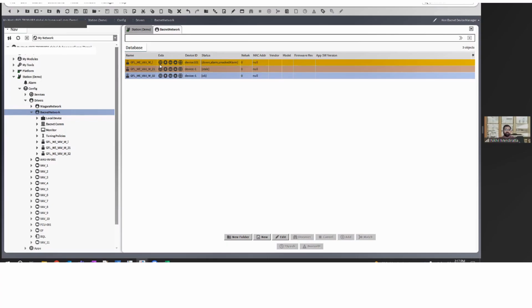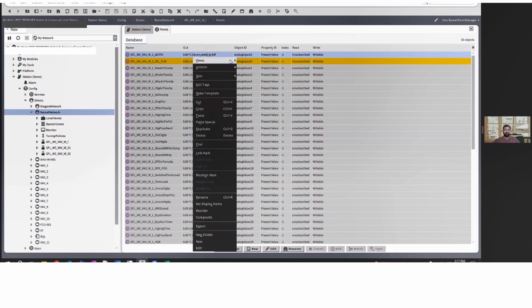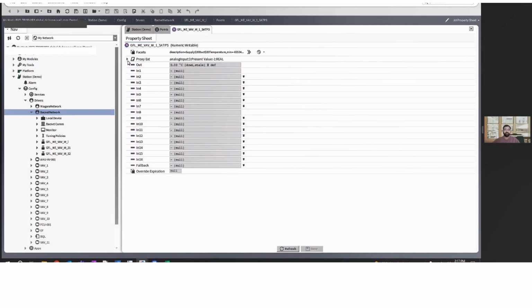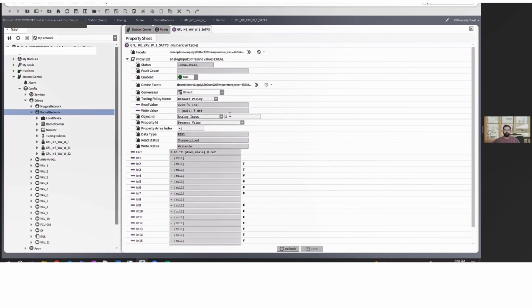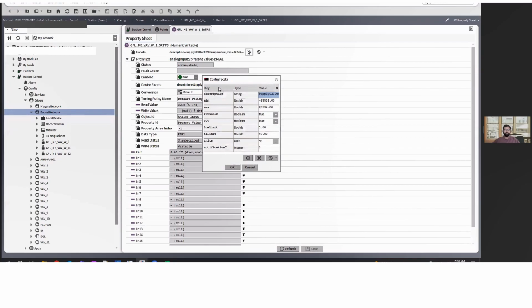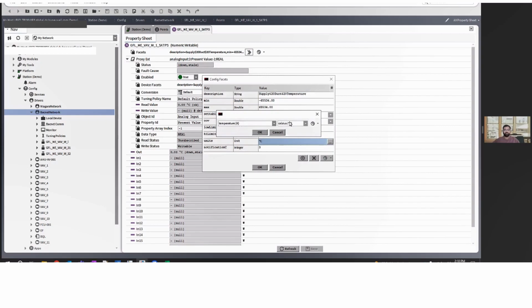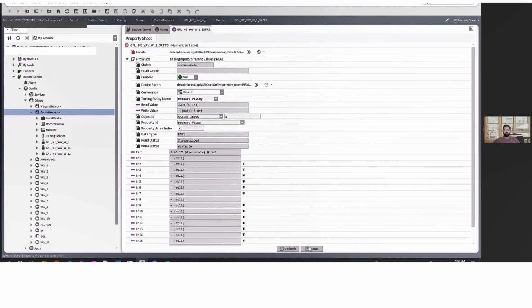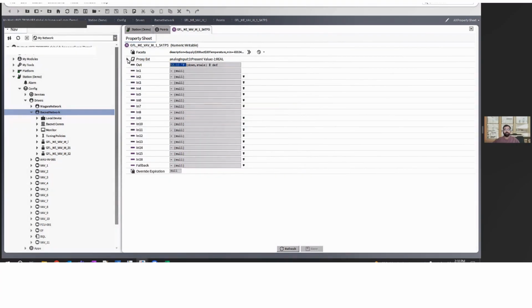There are two to three things we can discuss here. If we go into a point, let's say this is SATPS, and the software has been developed using degree Celsius, the value you'd be reading will be in degree Celsius, but your job requirements are Fahrenheit. Niagara has a device facet and a facet. The device facet is what it's reading from the controller, and the facet is what it converts. So the easiest way is to open the facets and inside units change it to Fahrenheit, and Niagara will do an automatic conversion for you. Notice the read value is 0 degrees Celsius, which is offline, and it's automatically converted into 32 degrees Fahrenheit. That's the beauty of Niagara—you don't have to write any additional logics or conversions to change the values from Celsius to Fahrenheit.